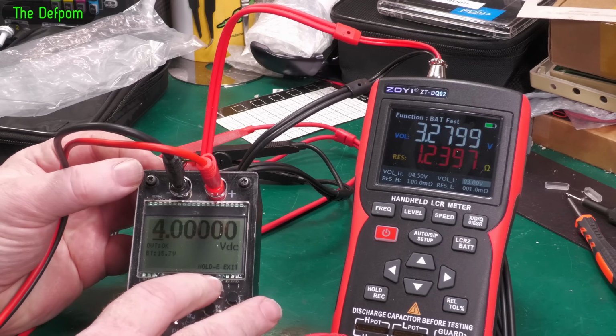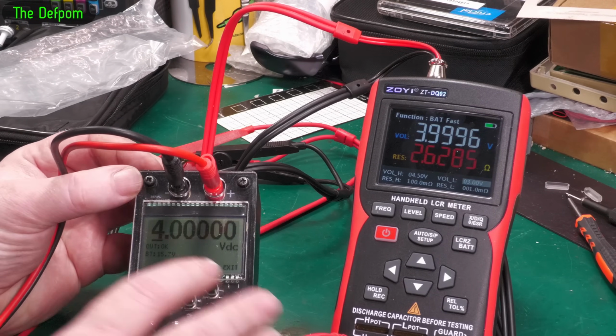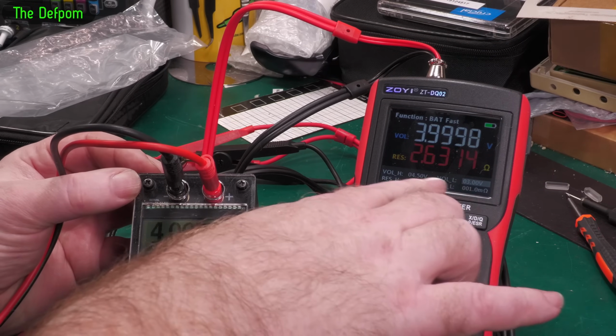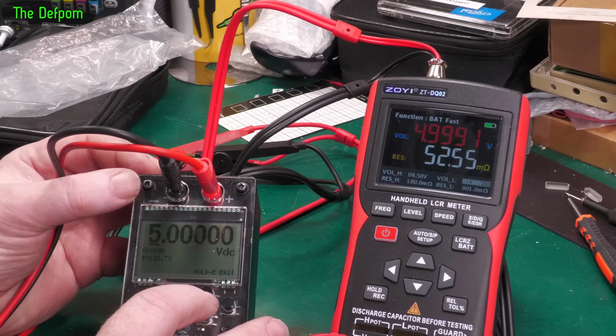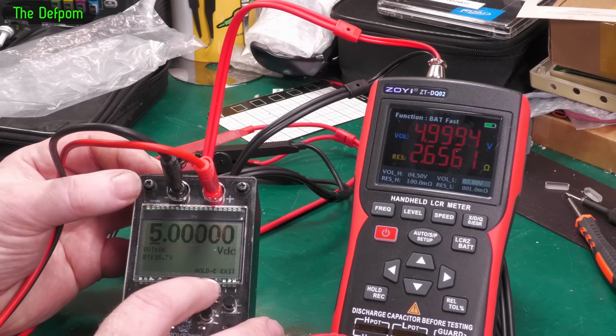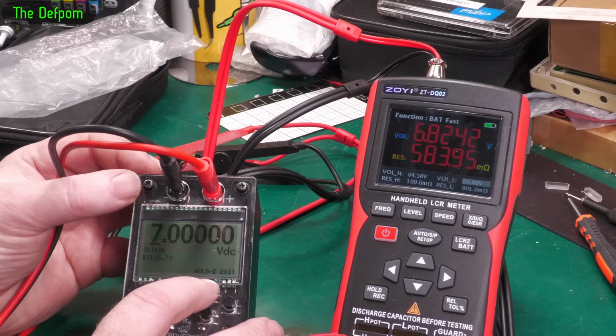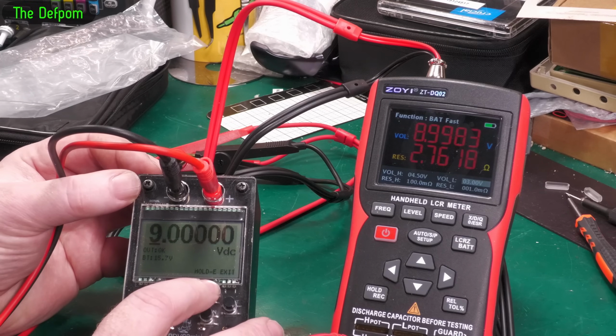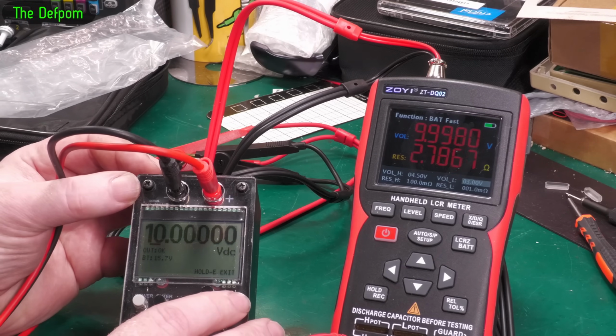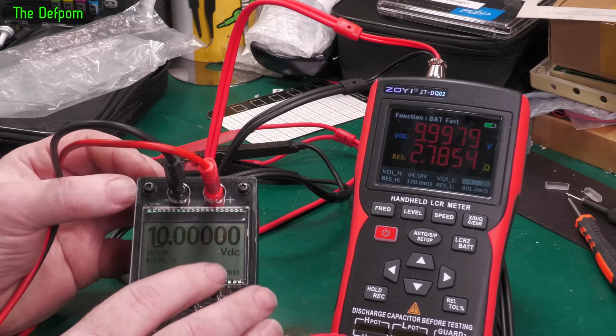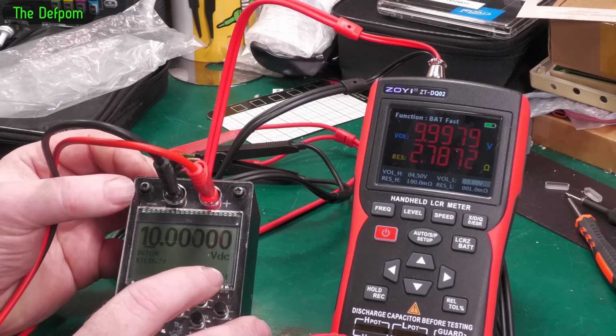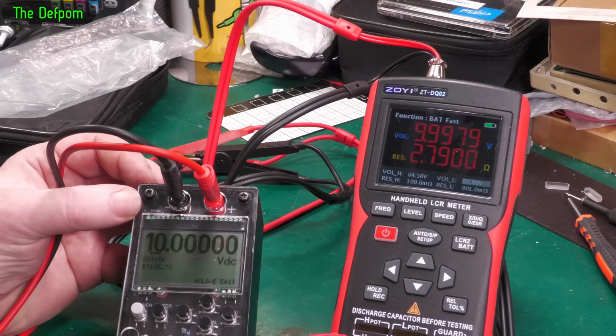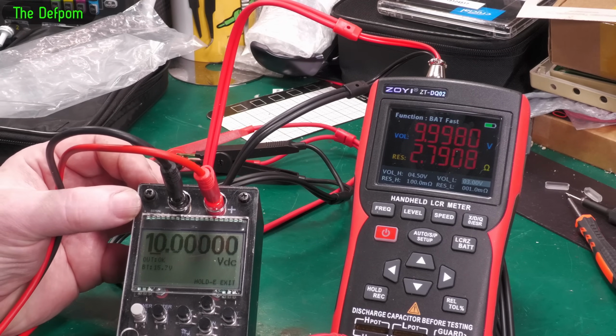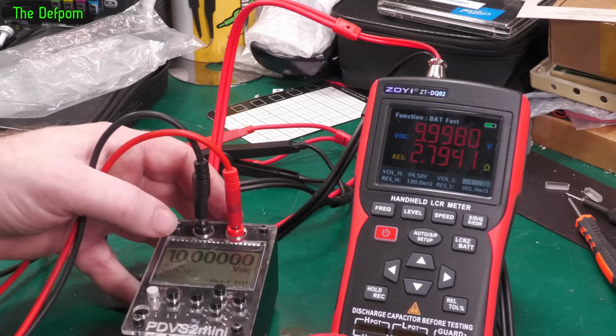Now the red is because it's got these tolerances set up here. So the red means it's outside that tolerance, see? And 10 volts - I mean, it's close enough, 2 millivolts out. I think for accuracy that's probably fine. It said like 5 counts and a certain percentage - I can't remember what the percentage was now, but that's actually looking not too bad.